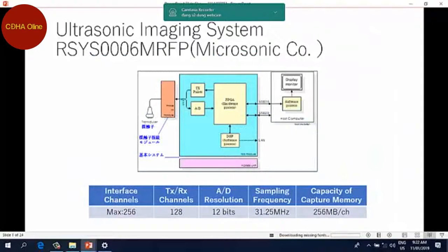This is the ultrasound imaging system. This is not a commercially available system. It was specially developed in this study, but the basic concept is the same as a commercially available system. The maximum interface channel number is 256. The channel count used is 128. The AD resolution is 12 bits, and the sampling frequency is about 30 MHz. The capacity of capture memory is 256 megabytes per channel.